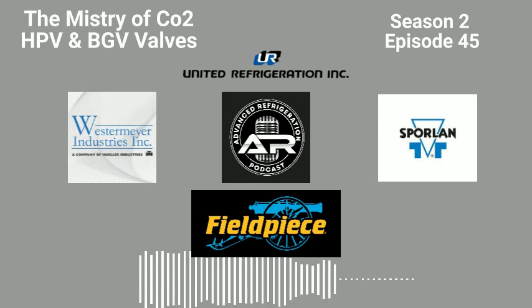Correct. And basically the BGV acts the same as the HPV, as an inlet pressure regulator. It's trying to relieve the pressure. If the pressure gets too high, it opens up and relieves that pressure into the medium temp suction, which is running 400 to 420. Yeah, about that, depending on what you're running, what your target is. So you have a flash tank at 500 pounds, and you may have a medium temp suction at 400 pounds. So you have that big difference there, and that valve doesn't need to open up very much, 20%, 30%. Now that valve's opening percentage is going to change over time.